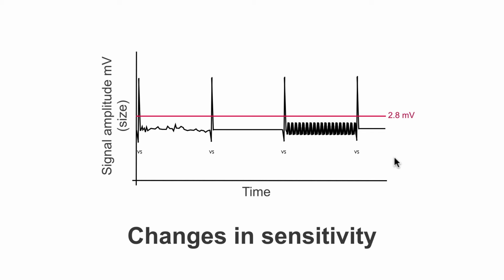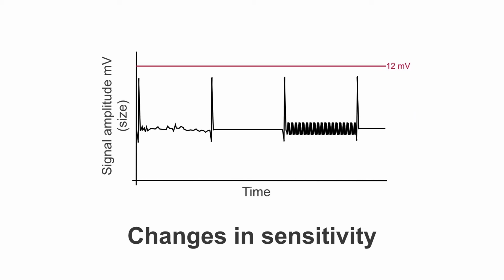Now, to make the device more or less sensitive, we can actually change the sensitivity. I just want you to be a little bit cautious about the terminology, and I'll explain why. By increasing the sensitivity, we make the pacemaker less sensitive. Let's have a look at an extreme example so we understand that concept. If I was to change the pacemaker sensitivity to 12 millivolts, it wouldn't detect anything that we've seen so far. Therefore, we've increased the sensitivity and made the device less sensitive.